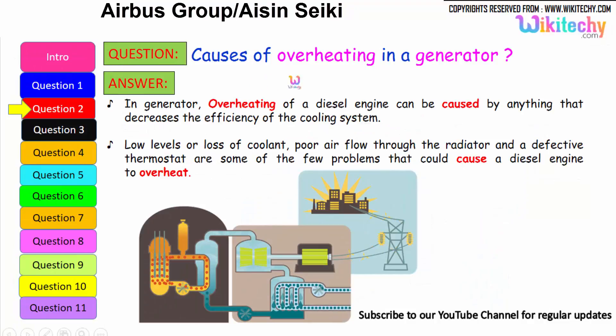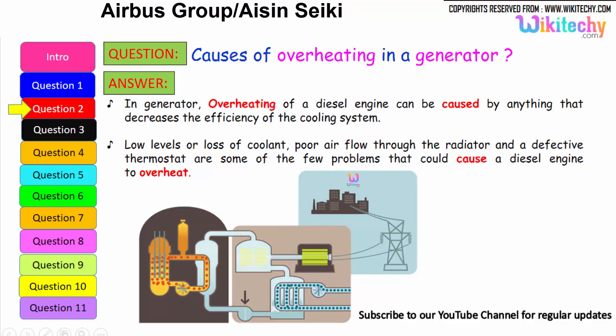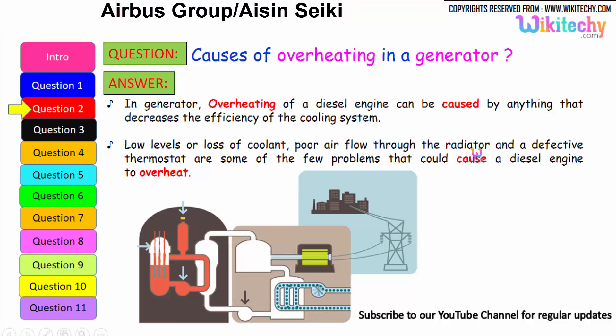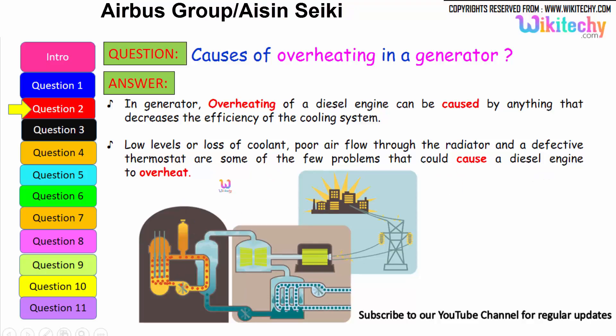Let us move on to the next question: causes of overheating in a generator. Overheating of a diesel engine can be caused by anything that decreases the efficiency of the cooling system. It can be due to the loss of coolant or low levels of coolant, poor air flow through the radiators, and a defective thermostat — these are some of the few problems that could cause a diesel engine or a generator to overheat.